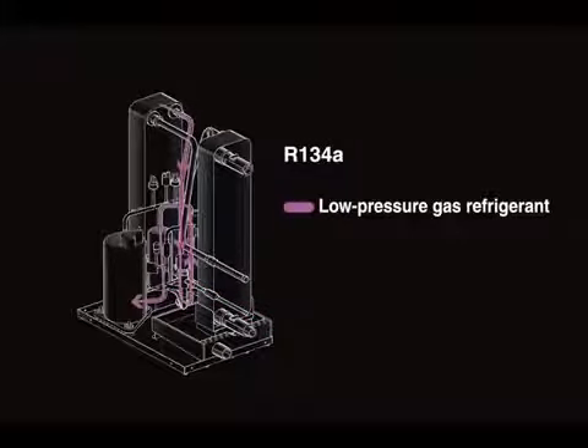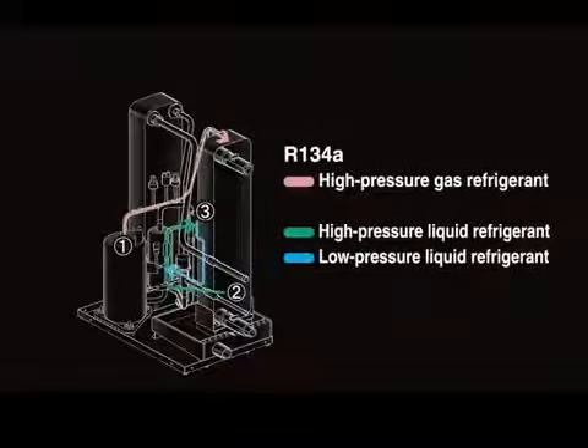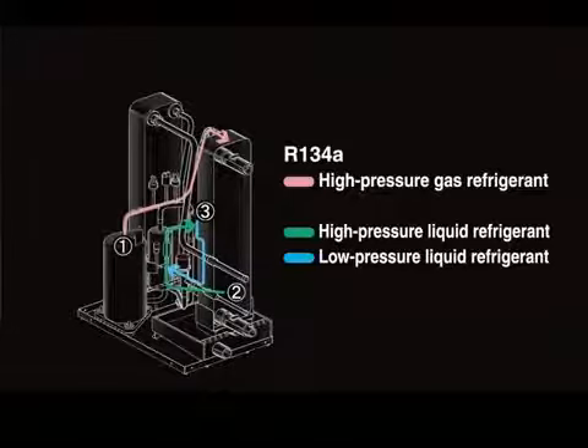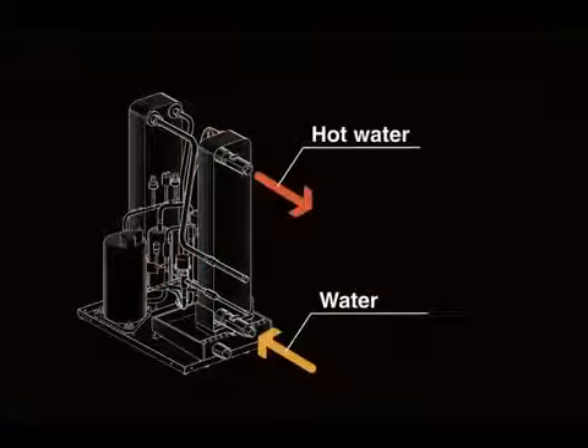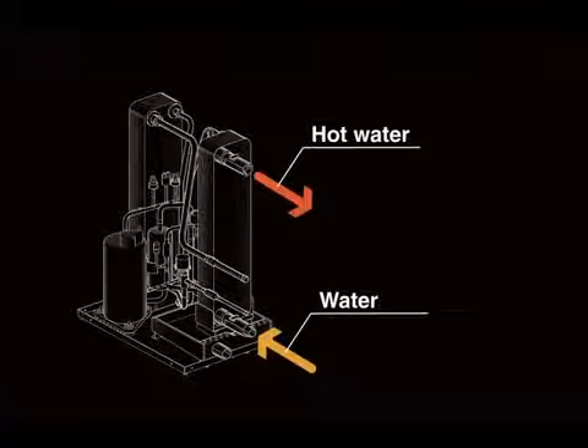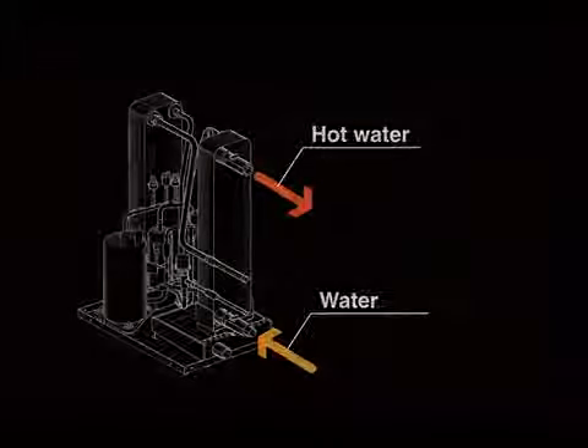To raise temperature, low-pressure R134A gas refrigerant is compressed by the compressor to become high-pressure gas refrigerant. Compared to the R410A refrigerant, R134A refrigerant requires less pressure to raise the temperature. To supply hot water, high-pressure R134A gas refrigerant is heat exchanged with the water entering the booster unit.